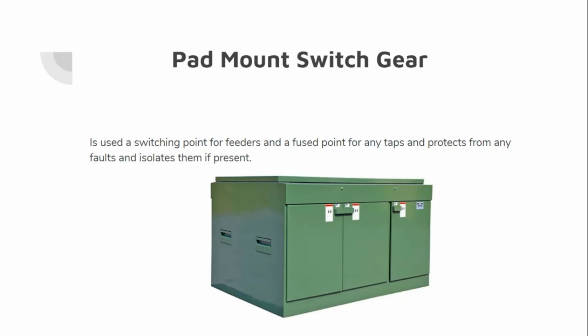All right, it's a switching point for feeders and it has taps, and those taps are fused. So you have isolation in case you have bad underground. That's a very good one. Good picture too.